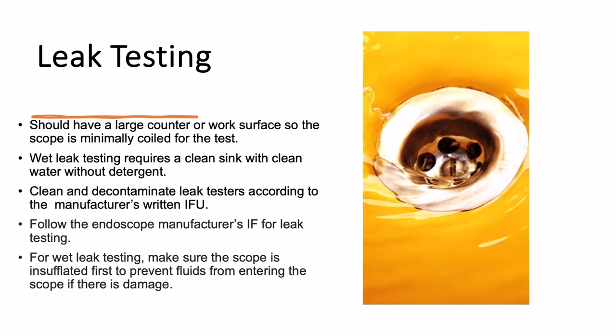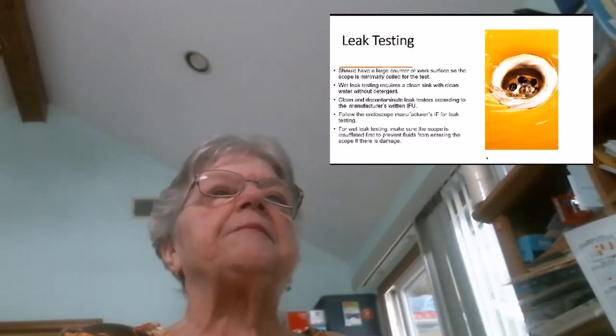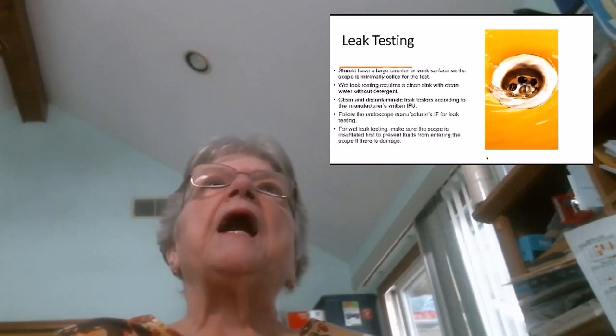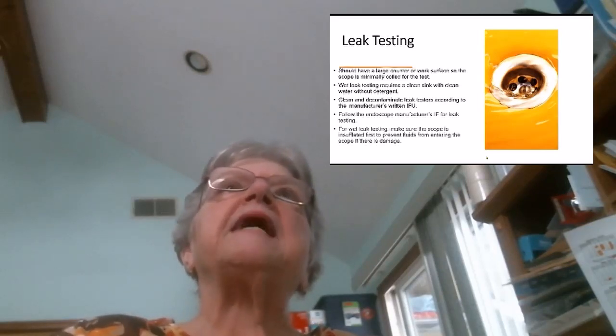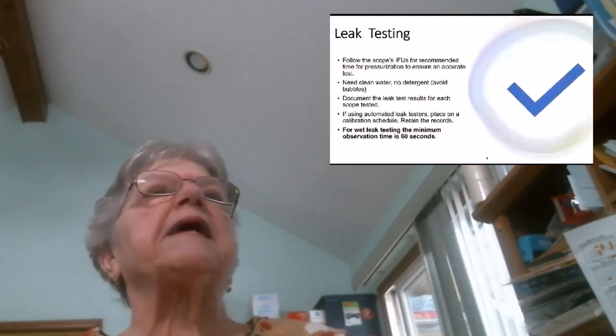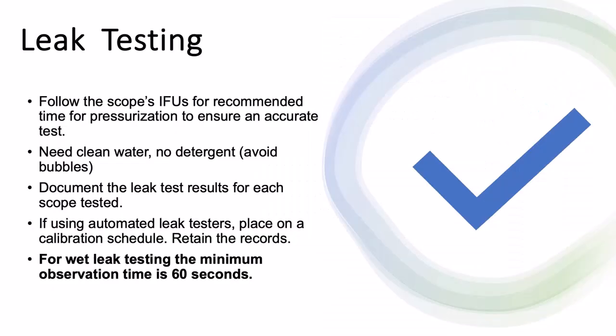And for wet leak testing, make sure the scope is insufflated first to prevent fluids from entering the scope if there is damage. So you're going to pressurize the scope. And once you do that, if it does have a breach when you put it into the solution, the pressure is not going to allow the water to get in and make that damage worse. Follow the scope's instructions for recommended time for pressurization to make sure you get an accurate test. Again, clean water, no detergent.